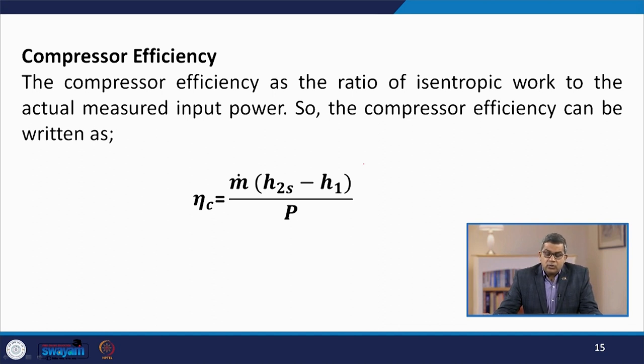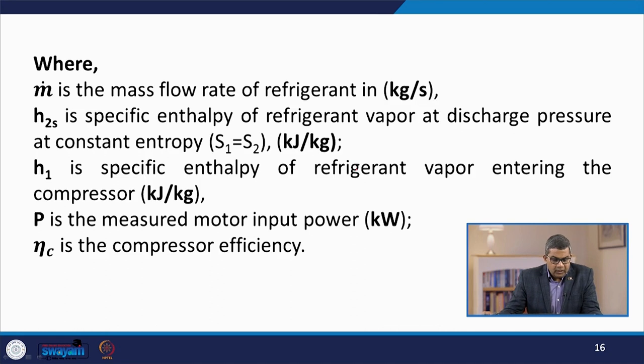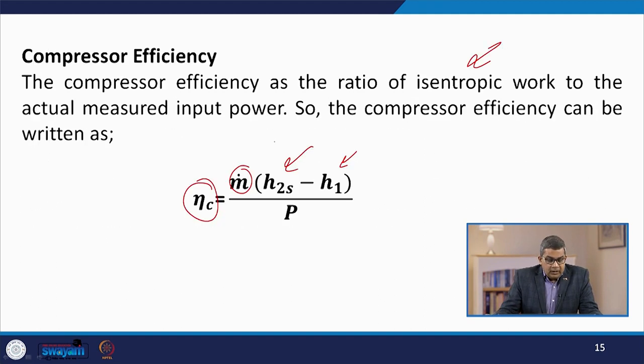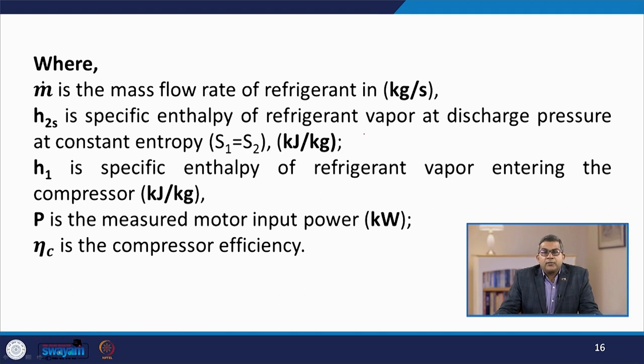Compressor efficiency is defined as the ratio of isentropic work to the actual measured input power. The formula is: η_c = m × (h₂s − h₁) / P, where m is the mass flow rate of refrigerant (kg/s), h₂s is the specific enthalpy of refrigerant vapor at discharge pressure at constant entropy with s₁ = s₂ (kJ/kg), h₁ is the specific enthalpy entering the compressor (kJ/kg), and P is the measured motor input power (kW).